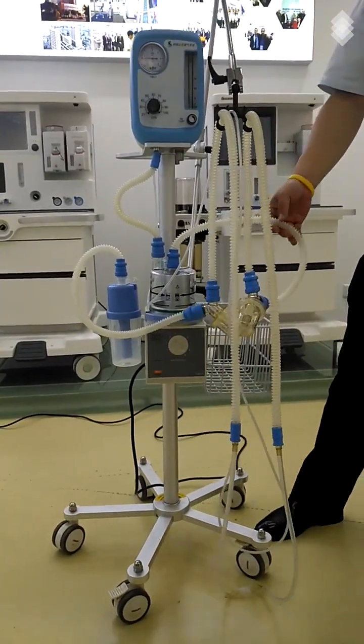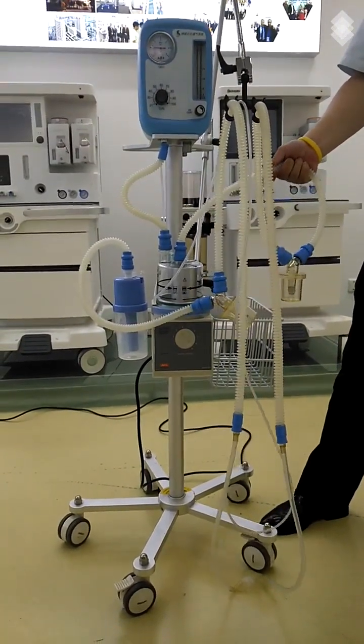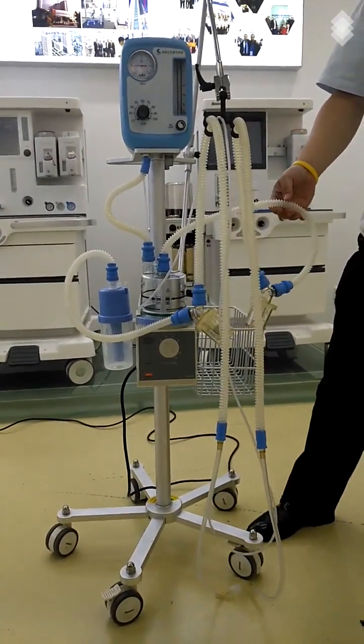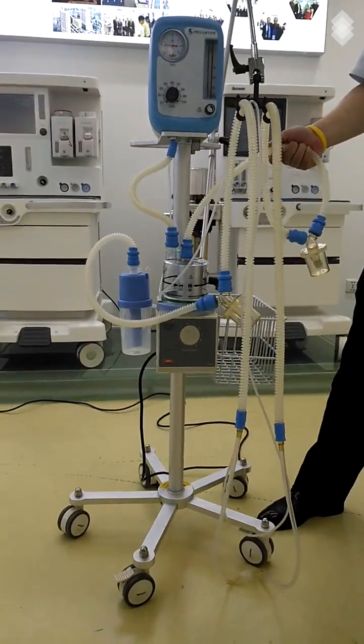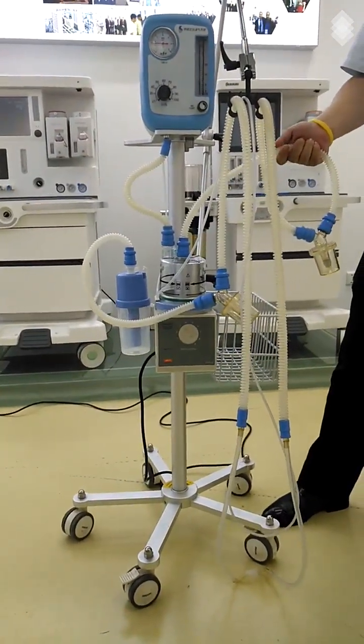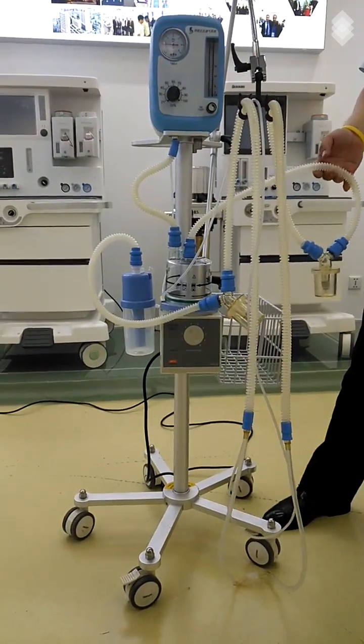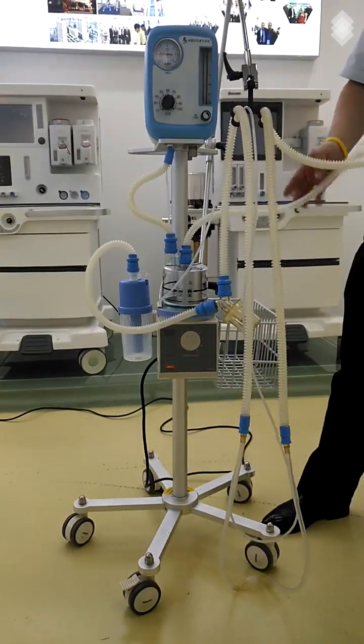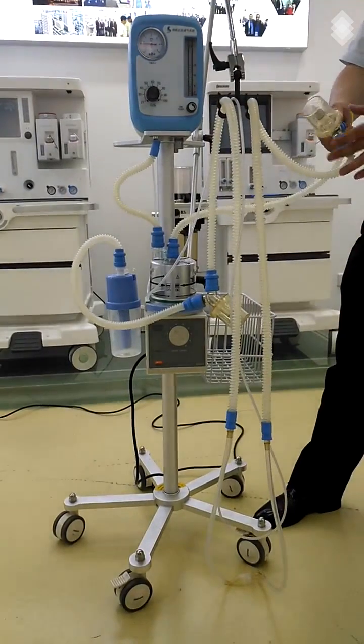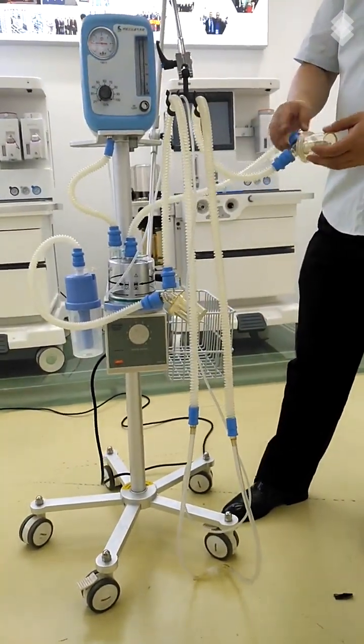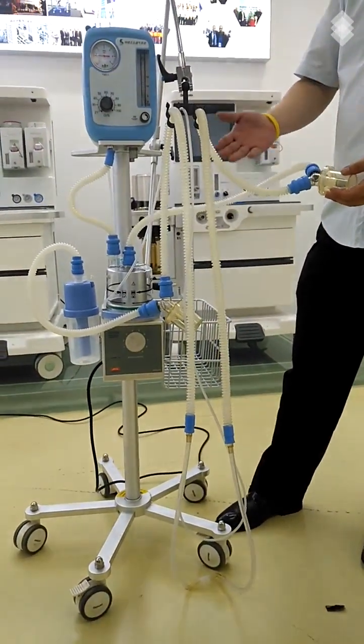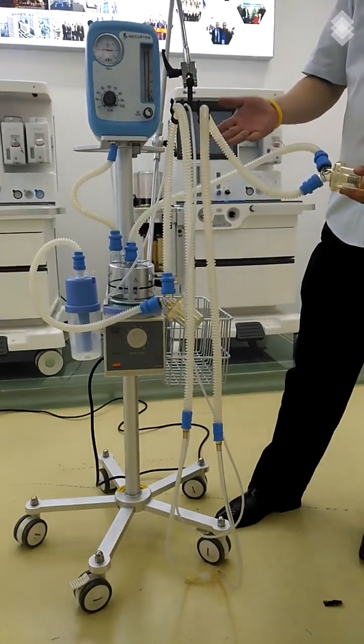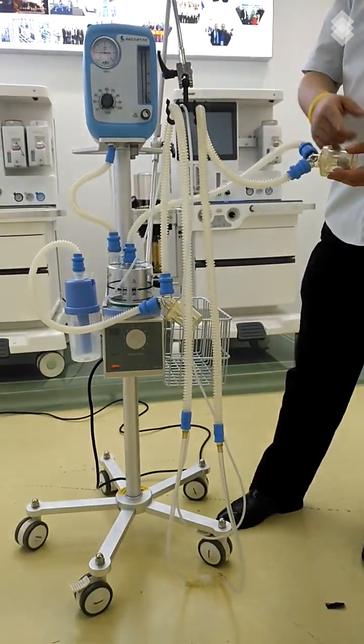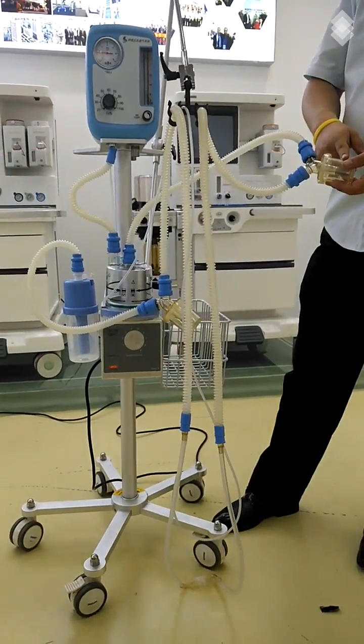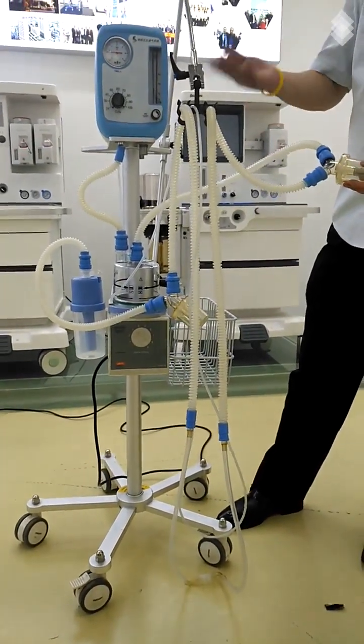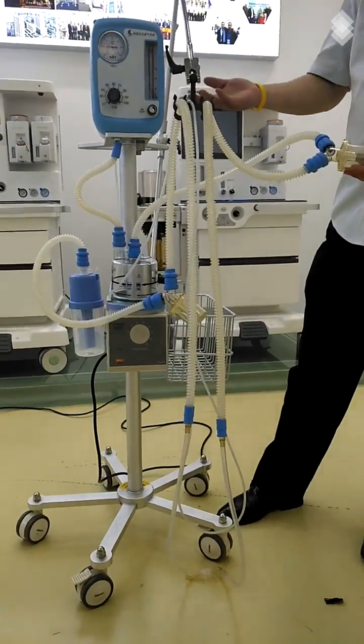For the pipeline here, we are using a total of 5 pipelines, three short ones and 2 long ones. We are using reusable pipelines, made of silicone, which can be cleaned at 134 degrees. Here, between the 2 pipes, we are using a water trap. This water trap is for holding water, because the humidifier generates heat and wetness in the gas. So there will be some water inside the water trap, so the water will not get into the baby's mouth or nose.